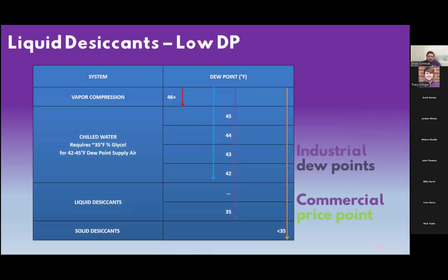So really quick, I want to recap on the low dew point of liquid desiccants. Vapor compression really can get down to about 46 degrees. Chilled water can go down to about 42. You really have to start looking at 35% glycol at those levels. And then liquid desiccants can get down to about 35-degree dew points, and below that is solid desiccants. So this is really your spread of systems.